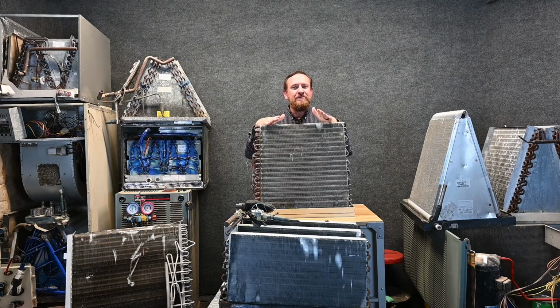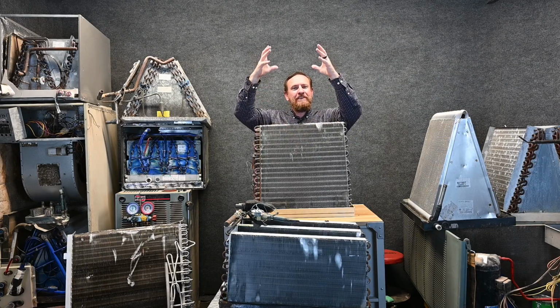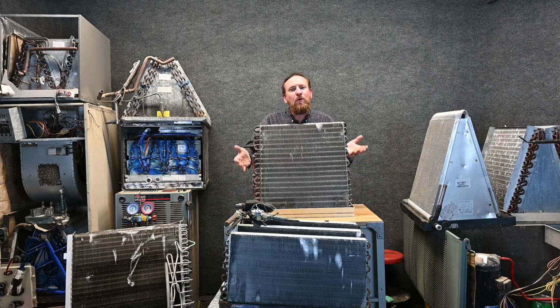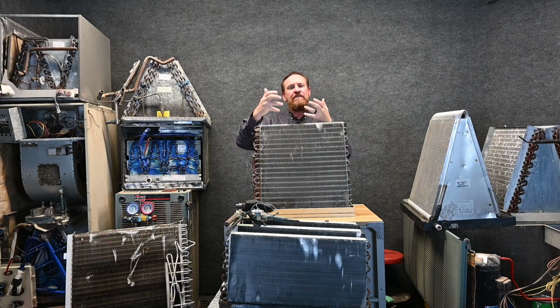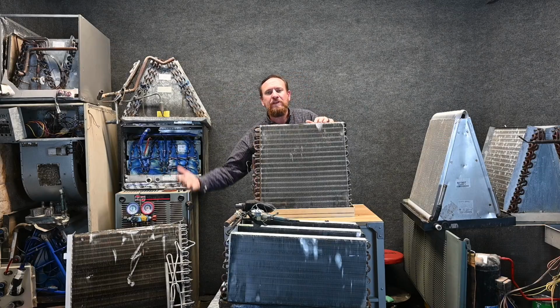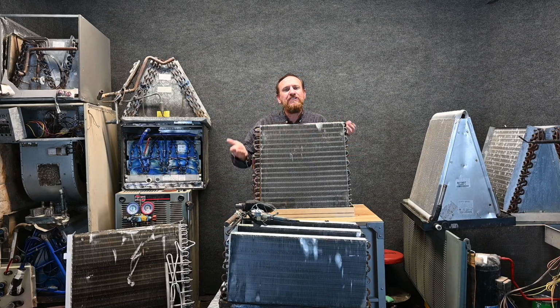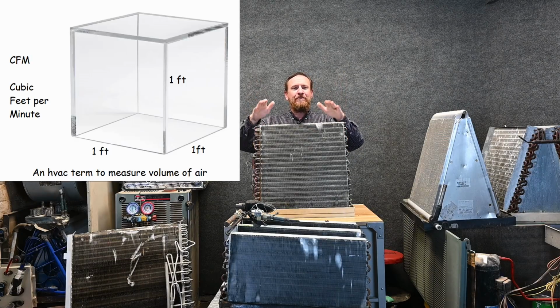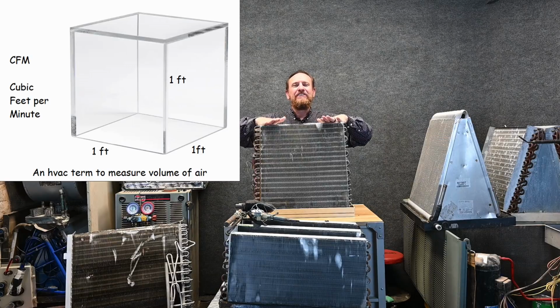And depending on the system design, we can have the blower above it. This is called negative pressure, where we pull the air across that evaporator coil. So it's sucking the air through the evaporator coil. Or I can have the blower down below and I can push the air across this evaporator coil. Whether we pull X number of CFM or we push X number of CFM, we need a certain CFM through that evaporator coil. How much?